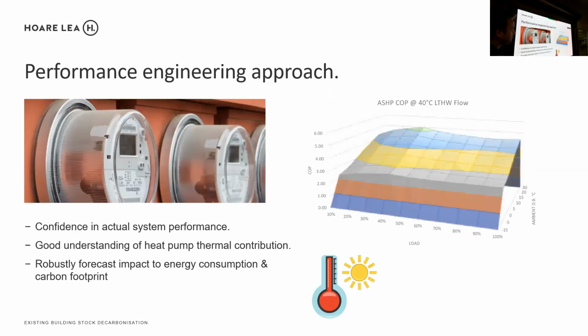The beauty, I think, of existing buildings is hopefully you can get a load of data. We had half-hourly meter data for every single installation for gas and electricity. So we knew exactly how those buildings performed. So we took that data and through analysis of the gas data, we could work out what the heating load was for every half-hour period. And then by mapping in a weather file, again, half-hourly weather data given the external temperature, we could work out exactly what the performance of the air source heat pump system would be, because we had part load data based on external temperature and flow temperature.